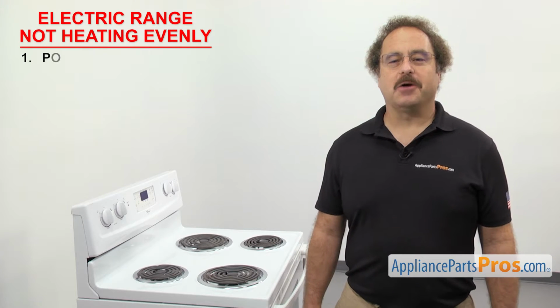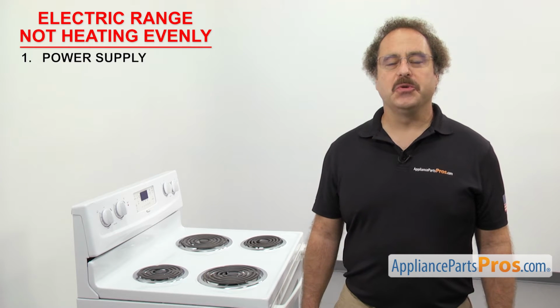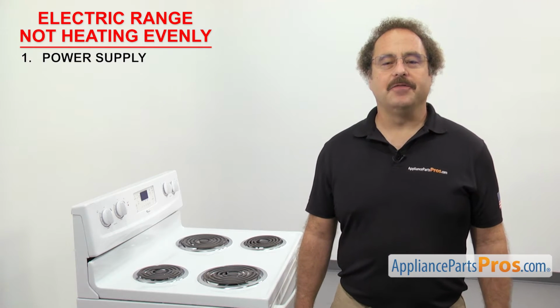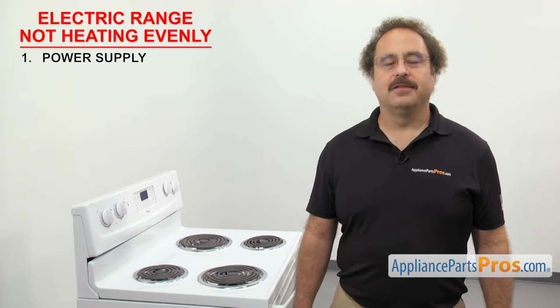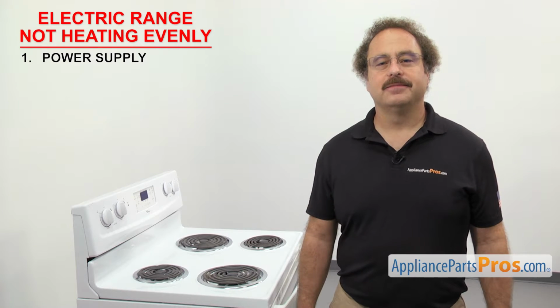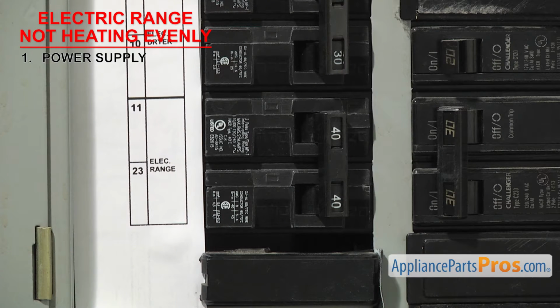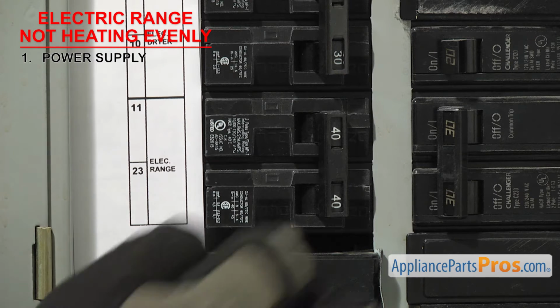The first thing to check is the power supply. Electric ranges need a full 240 volts to heat properly. If you only have 120 volts coming in, the lights may come on, but the range won't heat. So you'll need to go check the circuit breakers. Whether they're tripped or not, we're going to reset them.